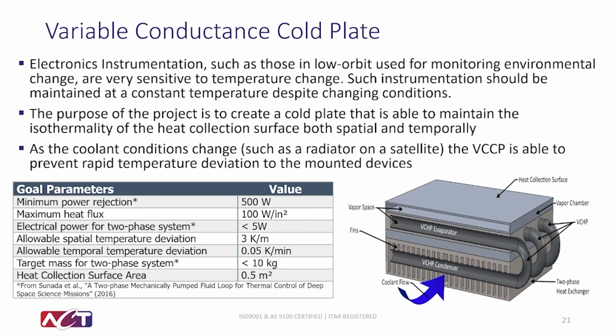Beneath the vapor chamber are variable conductance heat pipes, which not only transport the heat to a two-phase heat exchanger, but also provide the temporal isothermality in this system. A non-condensable gas takes up residence within the heat pipe condenser, and as the sink temperatures or the heat loads change, the gas expands or retracts, covering or revealing portions of the heat pipe condenser. This is what gives the heat pipe its variable conductance.